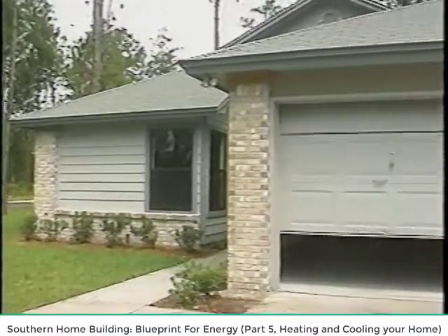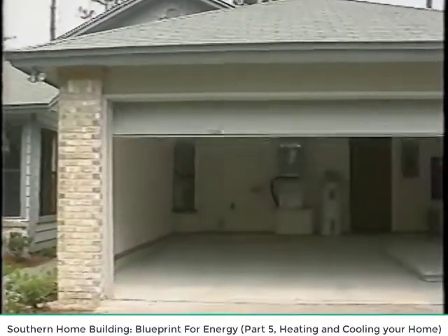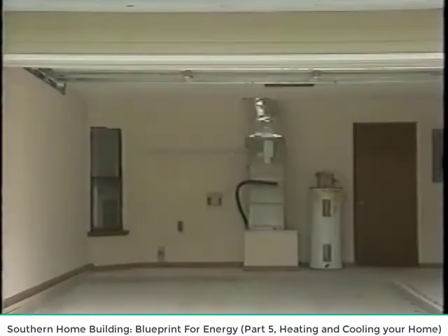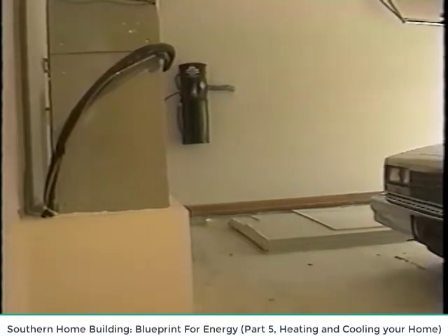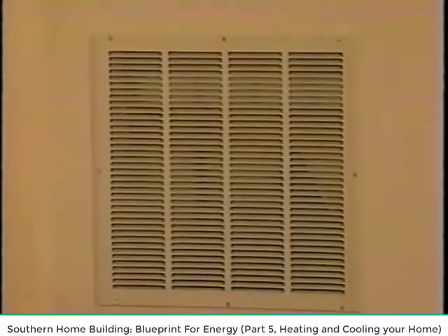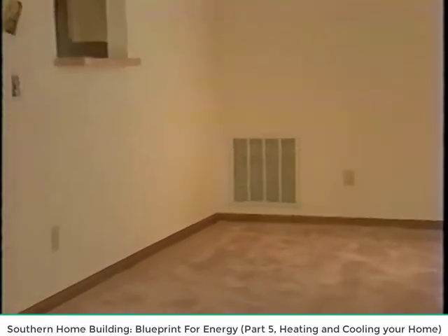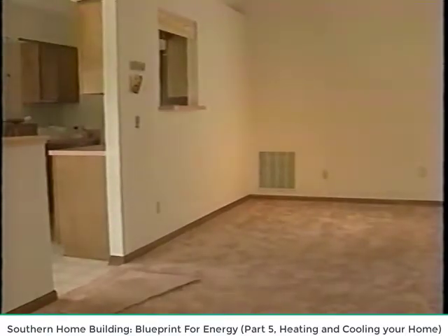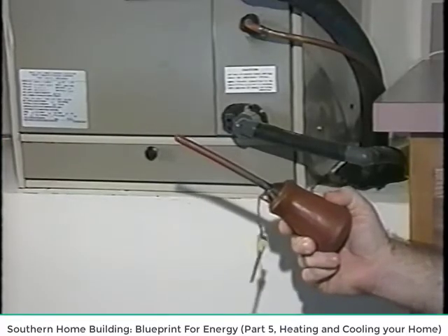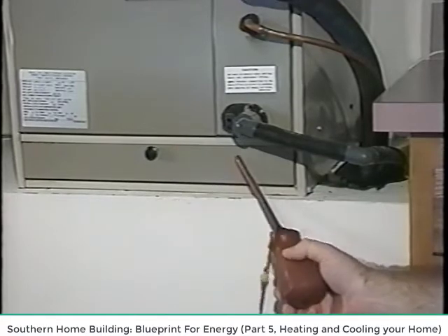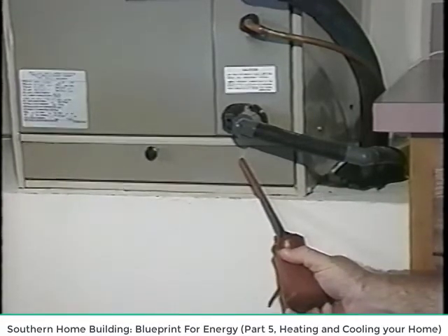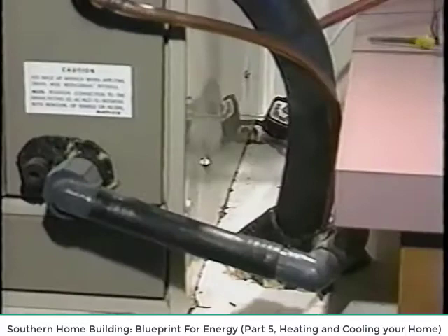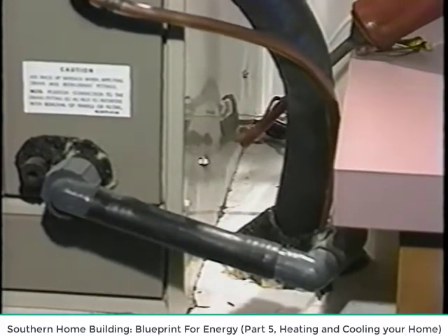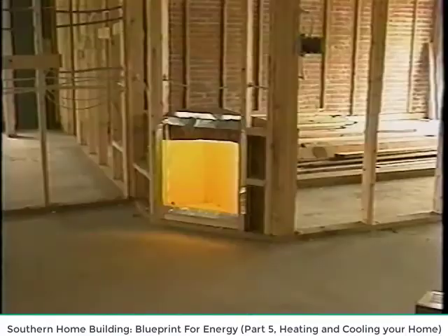If the air handler cannot be located inside, the second best place is the garage, but keep a free air return. To create the free air return with the air handler in the garage, use a grill through the wall between the house and the garage. There are 2 drawbacks to this location. Remember, air handlers usually leak, so valuable conditioned air is lost into the garage. Also, the air handler support box leaks. The support box needs to be sealed and insulated.